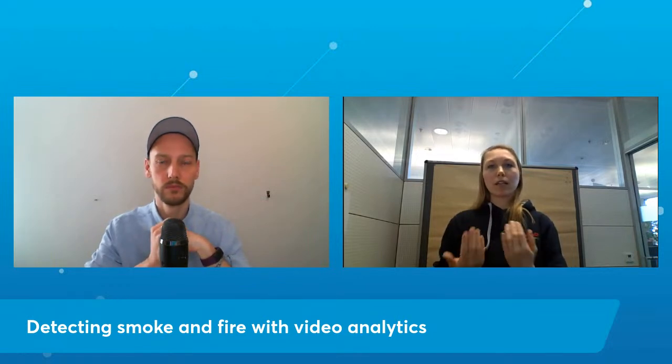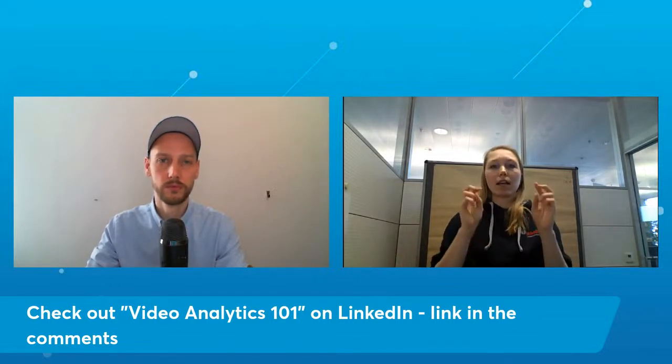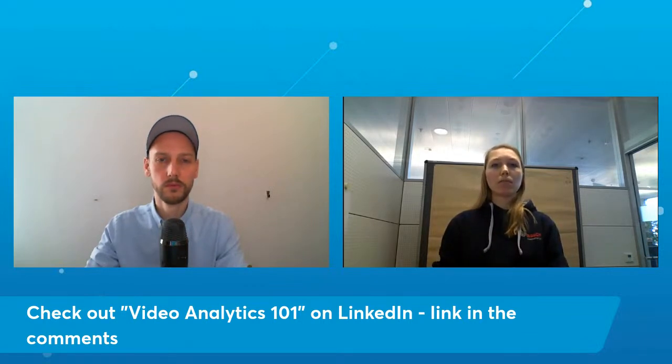And therefore, you've got different setting possibilities also in the camera. So you can compare it a little bit with standard smoke detectors, because there also you've got setting possibilities. If it is a more harsh environment, so more movement around or more people going on or objects are moving, then you can set the camera to a lower sensitivity so that it's kind of a higher robustness against these influencing factors. But this is what VDS is, for example, doing. It's a certification body. They are every time testing in the most robust way, because we want to make sure that also in these settings we are detecting fires.